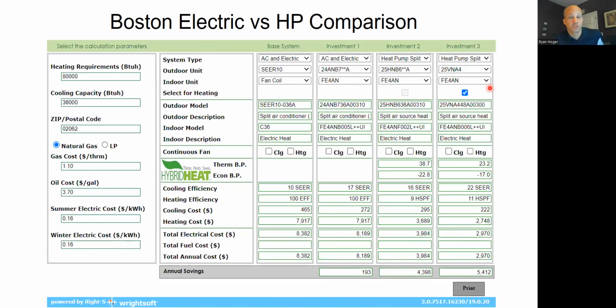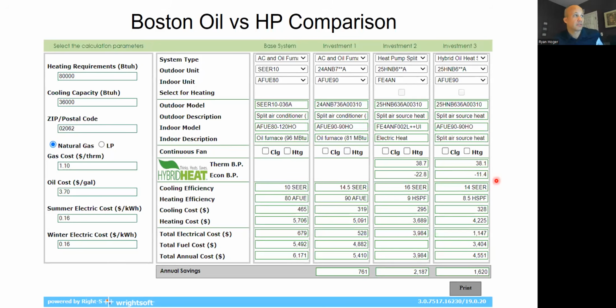This model of heat pump, which was an inverter driven, cold climate type heat pump, had a thermal balance point of 23, meaning below 23, I don't make enough BTUs for this exact heat pump and size in that exact building. And negative 17 is when it would be cheaper to actually run the other source, which is all electric.